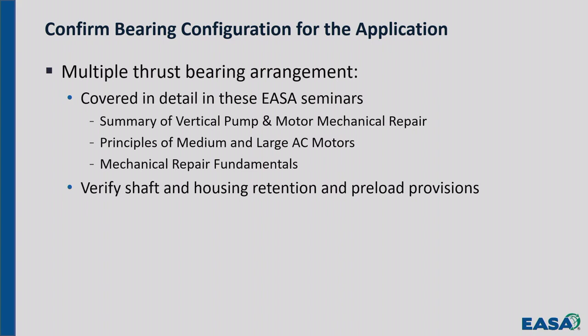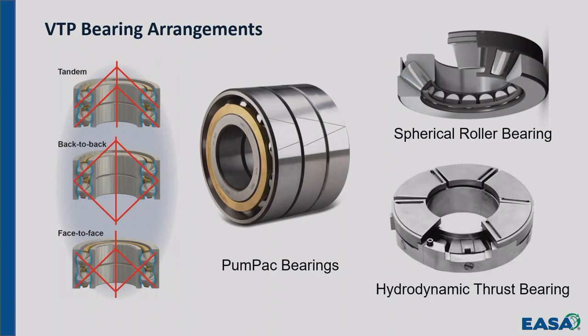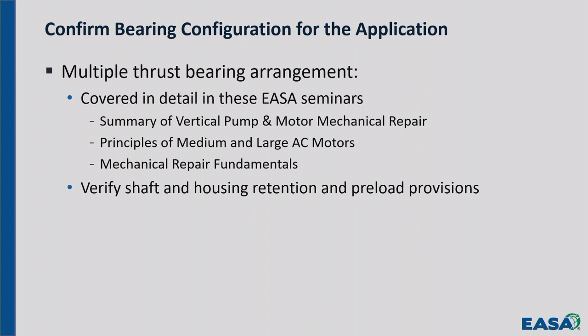When you're trying to decide which way these bearings go in, tandem, back to back, face to face, some of the hints that you get are in the housing and the shaft, with the way that the bearing is retained on the shaft and the way it's retained in the housing. I don't have time to go into it here today, but in those seminars we cover that. So somebody says, is this thing supposed to have one up and one down, or is this the one where they both go down? If you look at the way the shaft is configured and the housing is configured, there'll be hints about that. It doesn't always tell you what's right, but sometimes it'll tell you that it can't possibly be this one. If there's nothing holding the bearings down into the housing, you can't have a bearing configured for upthrust because there's nothing to hold the bearings. So the point is there are some hints there.